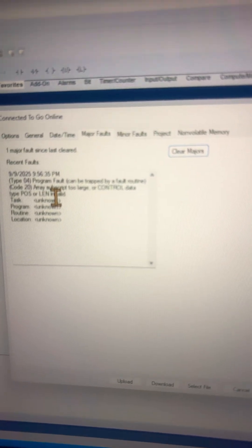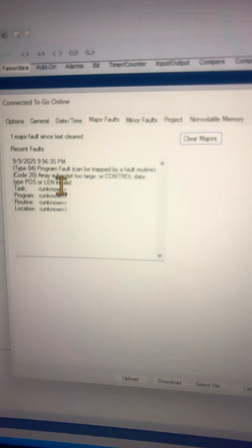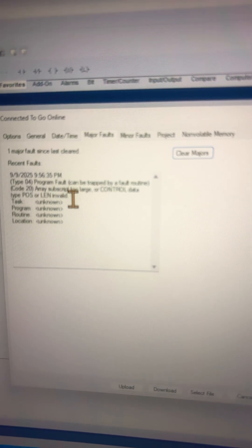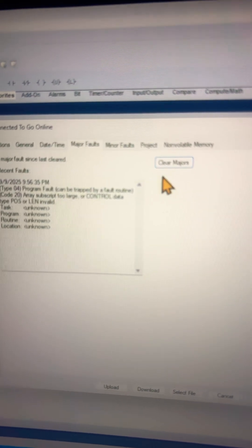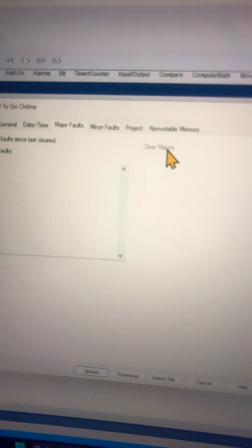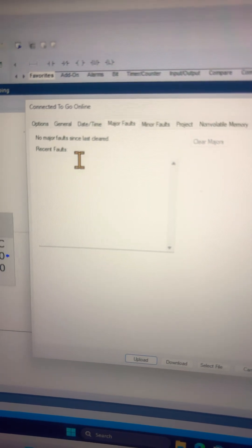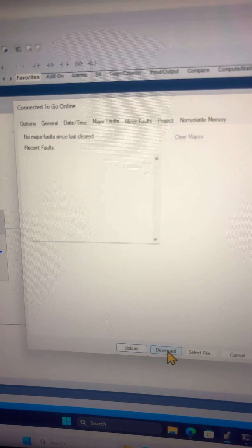We have an issue with the array being too short and we're trying to move to a position where the array index is not long enough. We hit Clear Major Fault; that will clear the fault, and now we can go ahead and hit the download.